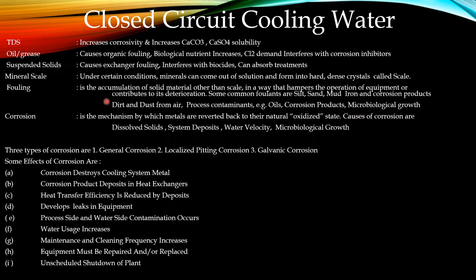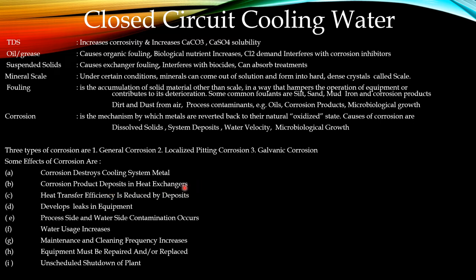Fouling also forms in pipelines and heat exchangers. Corrosion is normally due to TDS — it is the mechanism by which metals are reversed back to their natural oxidized state. Causes of corrosion include dissolved solids, system deposits, water velocity, and microbiological growth in the cooling water, all of which increase the corrosion rate. There are three types of corrosion: general corrosion, localized pitting corrosion, and galvanic corrosion. Corrosion will destroy the cooling water system metal and affect the metal surface of the cooling water pipeline. Corrosion product deposits on the heat exchanger tube side reduce heat transfer efficiency.